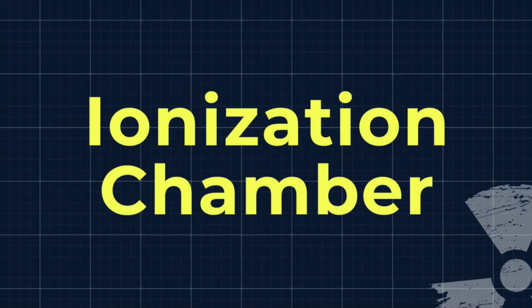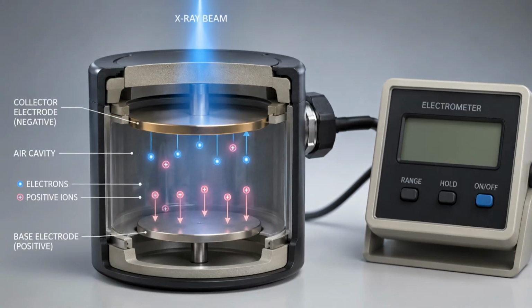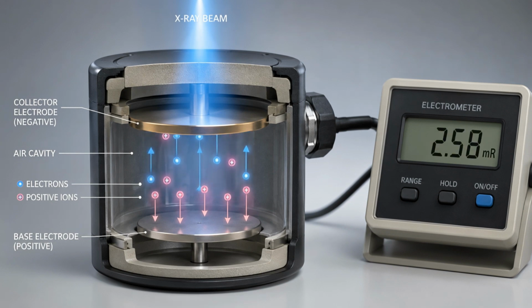Exposure equals the charge that exists within air, and it's measured using an ionization chamber. An ionization chamber is basically a tool that measures radiation by using ionization itself. Inside the chamber, you've got a known volume and mass of air, or another gas. When X-rays or gamma rays pass through, they ionize the atoms inside, freeing up electrons and creating positive ions. Those freed up electrons and ions get collected by two oppositely charged plates, and from there we can measure that electrical charge and express it in coulombs per kilogram.